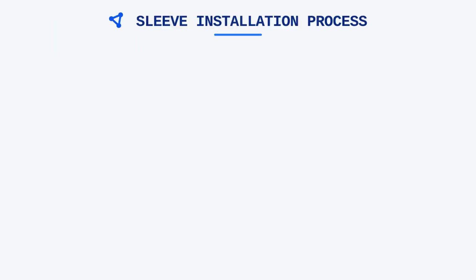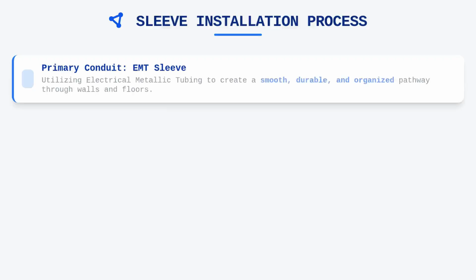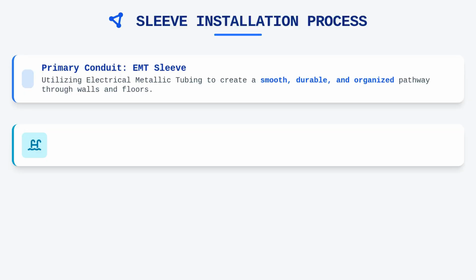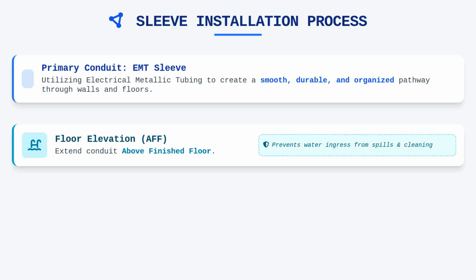Once we have confirmed the safety of a location, the installation of a sleeve becomes our primary method for maintaining an organized and protected pathway. An electrical metallic tubing or EMT sleeve is typically employed to provide a smooth, durable conduit through the wall or floor. When placing these sleeves in floor assemblies, we must intentionally extend the conduit above the finished floor, often abbreviated as AFF, to a specific height. This elevation is not an aesthetic choice, but a protective measure designed to prevent water ingress from surface cleaning or accidental spills from infiltrating the pathway and damaging the enclosed cabling.